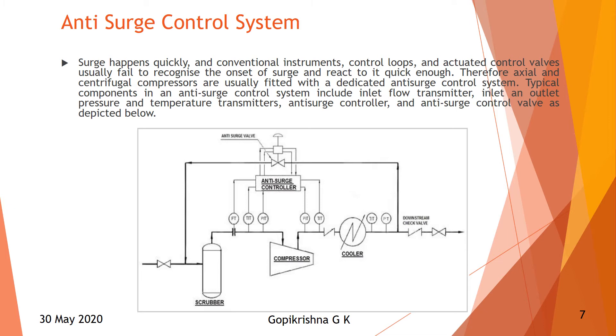The system layout includes a suction scrubber at the inlet, with flow meter, flow transmitter, temperature transmitter, and pressure transmitter at the suction of the compressor. All these control inputs are given to the controller, as well as discharge pressure and temperature. There is also a cooler after the discharge, with pressure and temperature transmitters. The discharge is connected through the anti-surge control valve back to the suction. Based on suction, discharge, pressure, and other conditions, the control valve will open and close to maintain the pressure balance.